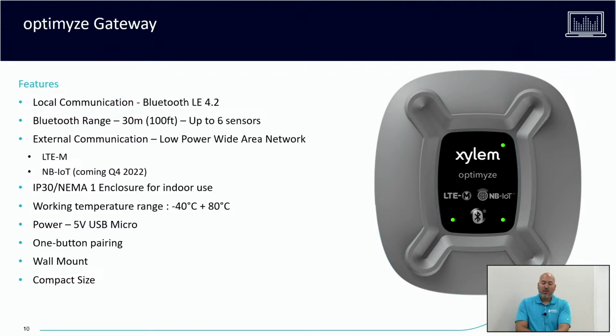But the low power wide area network is a little bit different than a cell signal. It sends smaller packages of data, and it's a little bit more successful at penetrating walls and things of that nature. So we know a lot of these applications, pumps and things, are going to be installed in mechanical rooms or basements that have limited cell service. So although you may not have good cell service next to this, that doesn't mean the gateway's not going to work, because it is using a different external communication, the low power wide area network, that is a little bit better suited for those environments.